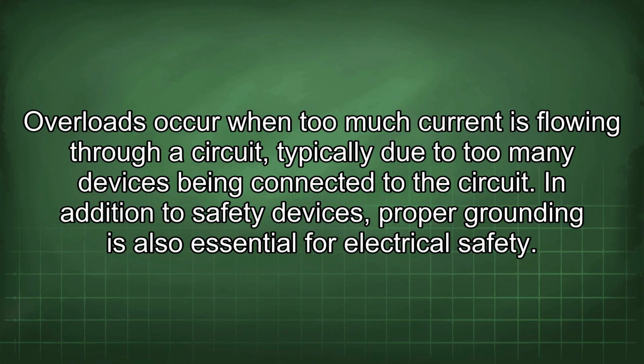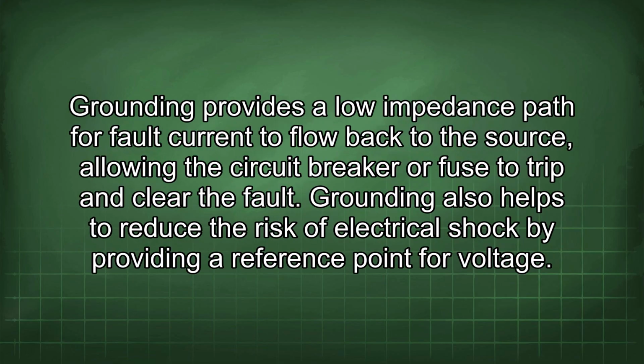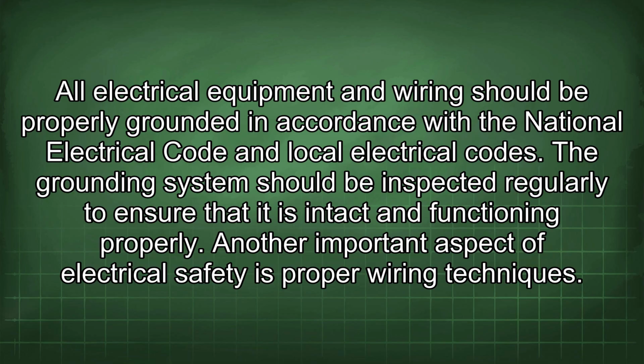In addition to safety devices, proper grounding is also essential for electrical safety. Grounding provides a low-impedance path for fault current to flow back to the source, allowing the circuit breaker or fuse to trip and clear the fault. Grounding also helps to reduce the risk of electrical shock by providing a reference point for voltage. All electrical equipment and wiring should be properly grounded in accordance with the National Electrical Code and local electrical codes. The grounding system should be inspected regularly to ensure that it is intact and functioning properly.